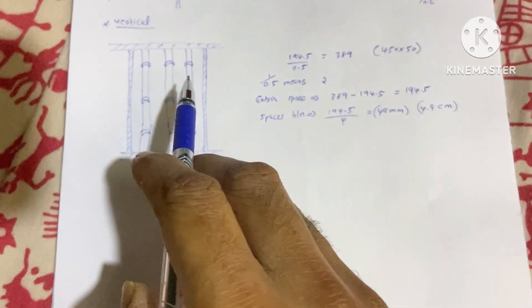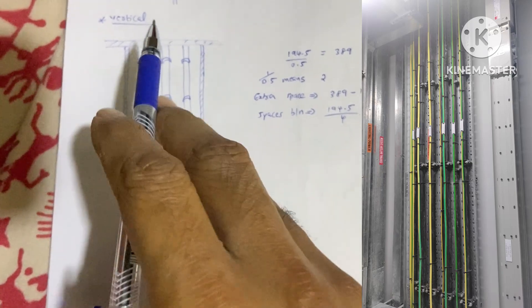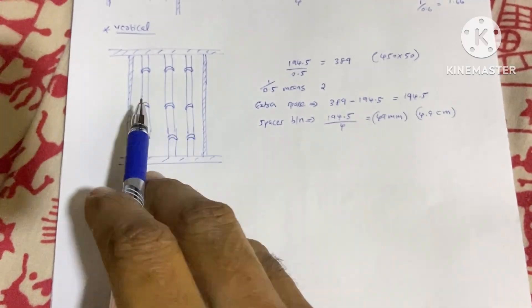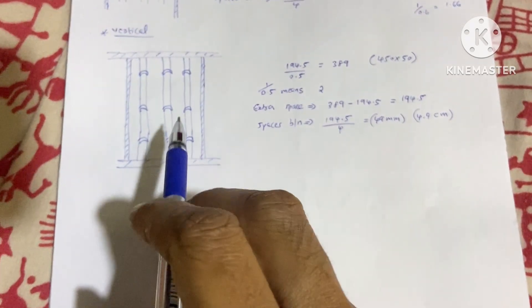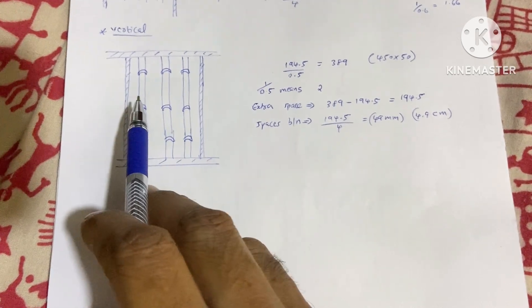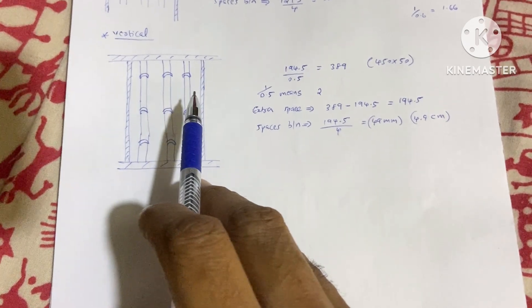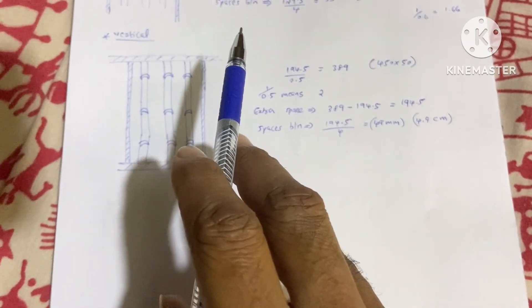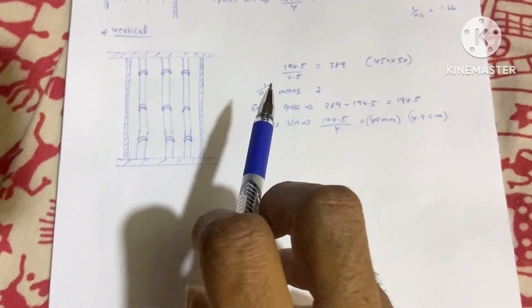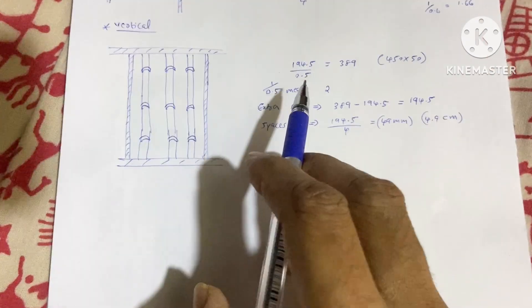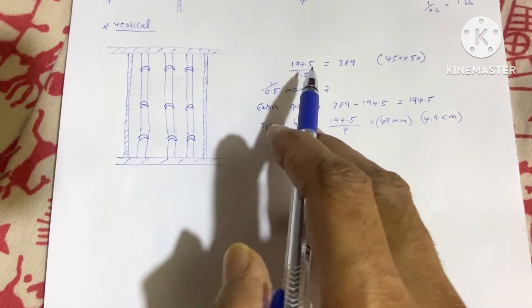Now I am going to calculate the cable tray size for a vertical cable tray. This is a sectional view showing the cable tray running from one floor to another through a cable tray riser. We have the same three cables as before — 300mm², 240mm², and 185mm² — so the total overall diameter remains 194.5mm.